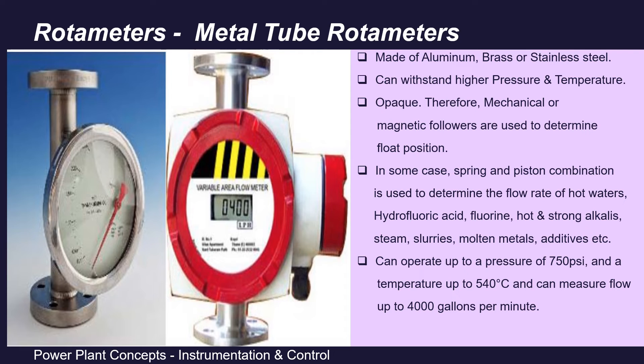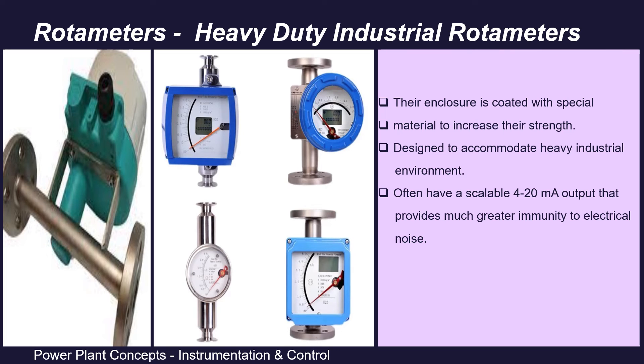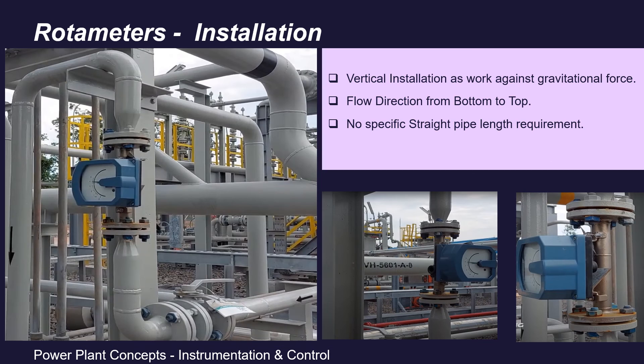Metal tube rotameters are suitable for hydrofluoric acid, fluorine, hot and strong alkali, steam, slurries, molten metals, additives, etc. They can operate up to a pressure of 750 psi and a temperature of 540°C, and can measure volumetric flow up to 4000 gallons per minute. The third type is heavy-duty industrial rotameters — these are flanged armored rotameters, with enclosure coated with special material. They are designed for heavy industrial environments and often have a scalable 4–20 mA output providing greater immunity to electrical noise.